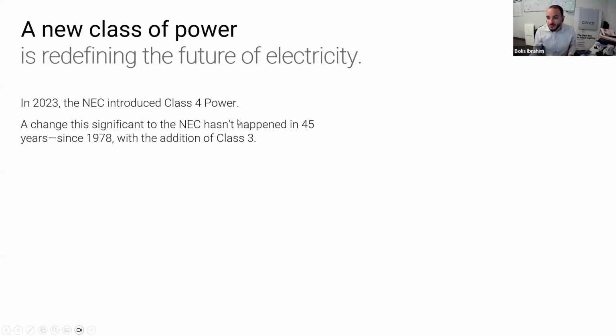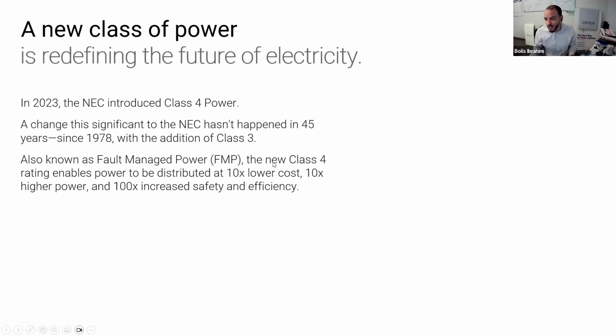So this is new. In 2023 the National Electrical Code introduced class 4. We don't have class 3 in Canada, that's a US thing. Class 3 is basically a special case of class 2. Oversimplification, but anyways, this is cool because class 3 was introduced in 1978. So it's been 45 years and now they're introducing class 4. So what's going on here? It's really cool. It's what's known as fault managed power.